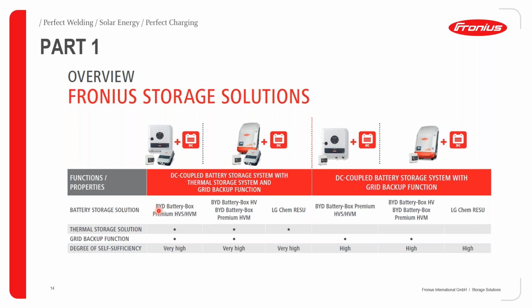It should either be the BYD battery box premium HVS or HVM. Okay. This also allows for a thermal storage solution to be incorporated. In our case, it is the Ohmpilot. It also allows for grid backup functionality integrated as well. And the degree of self-sufficiency is very high. Okay, so with such a system, you can actually ensure that your client can easily achieve a 90% plus self-consumption efficiency rate.